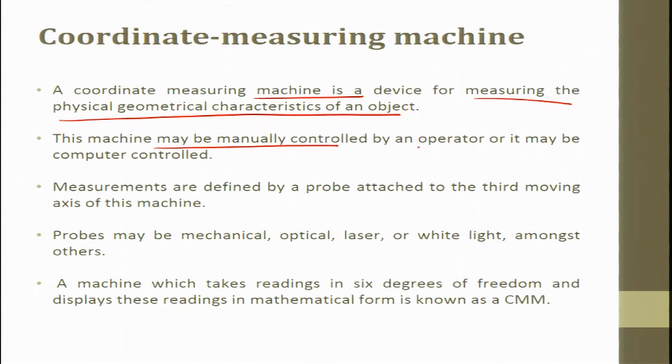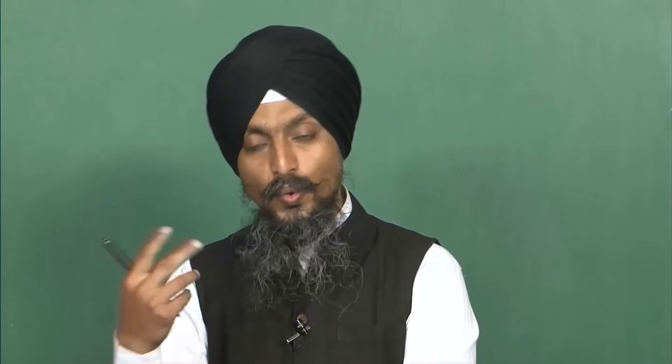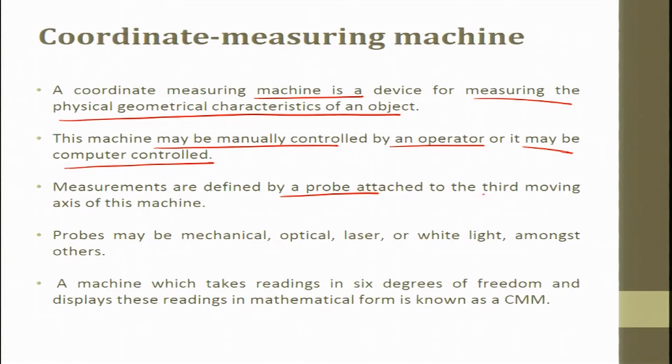This machine may be manually controlled by an operator or it may be computer controlled. We will show both operations — manual control using a joystick and CNC mode. CNC mode is computer numerical control: we give the initial point and define the distance — say after each mm or 2mm — and it records the points on a specific plane or curve. Measurements are defined by a probe attached to the third moving axis — the x, y, and z axes.